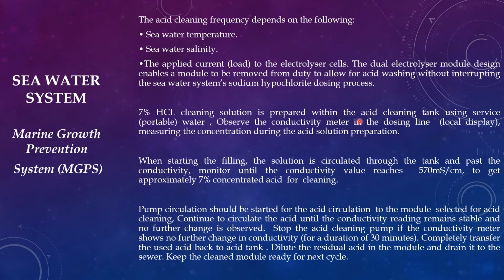7% HCl cleaning solution is prepared within the acid cleaning tank using service water or potable water. There is one conductivity meter provided in the line. We have to observe the conductivity meter in the dosing line and the concentration during the acid solution preparation. The concentrated acid will be diluted with potable water and we have to produce 7% HCl. Starting the filling, the solution is circulated to the tank and passed through the conductivity meter. When the conductivity value reaches 570 millisiemens per centimeter, the concentration will be roughly 7%, which is the required concentration for cleaning the module to remove the scaling.